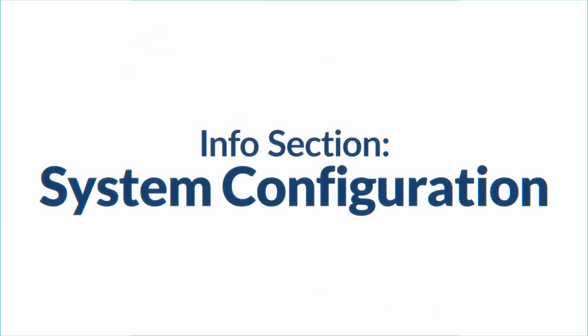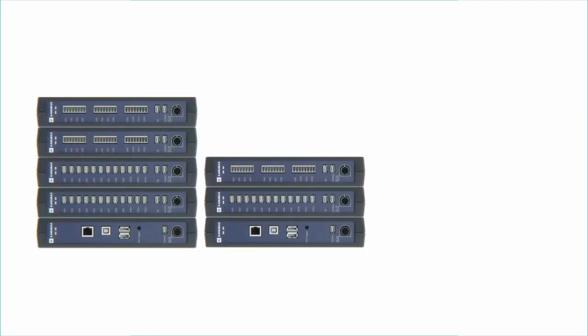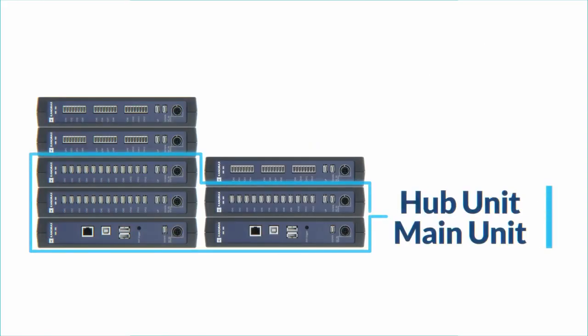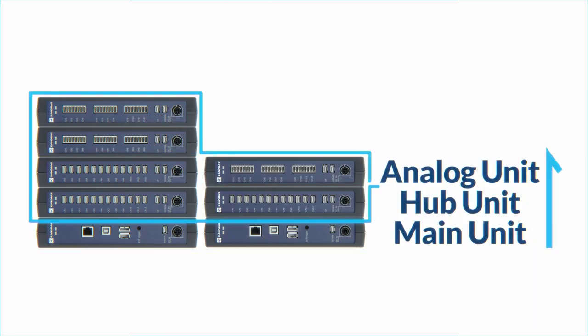Prior to powering on the units, it's important to ensure your system configuration is correct, otherwise malfunctions and/or damage can occur. No matter the number of units being used, the unit should be connected in the order of main unit to hub units, and hub units to analog units for the 1590. For the 1580, it's main unit to analog unit.